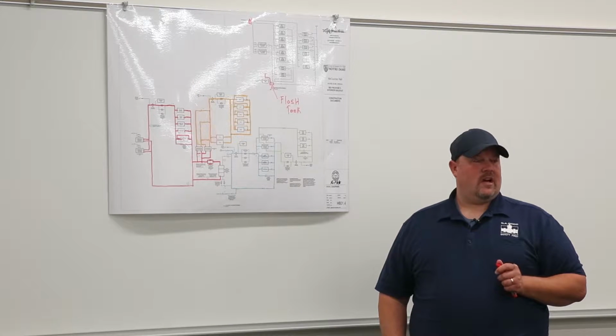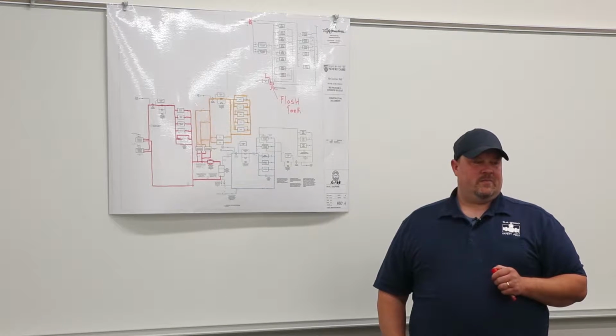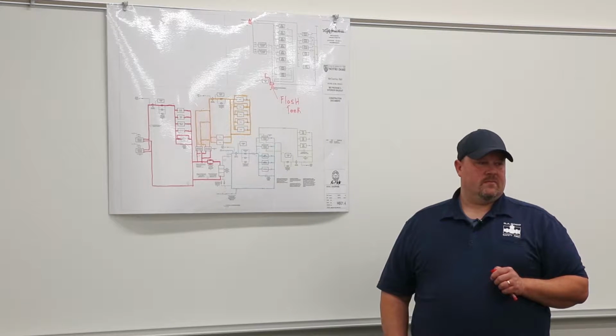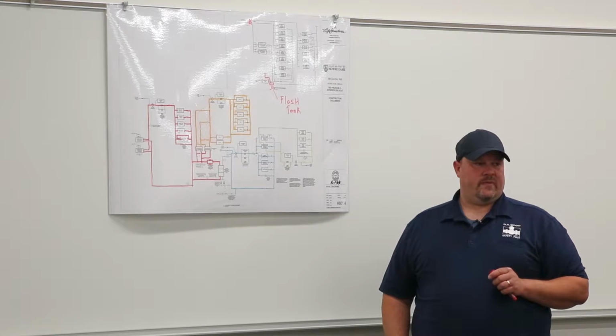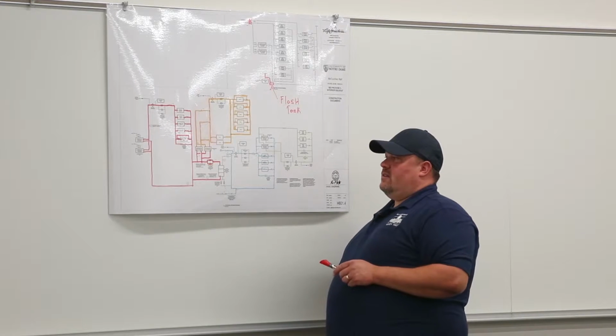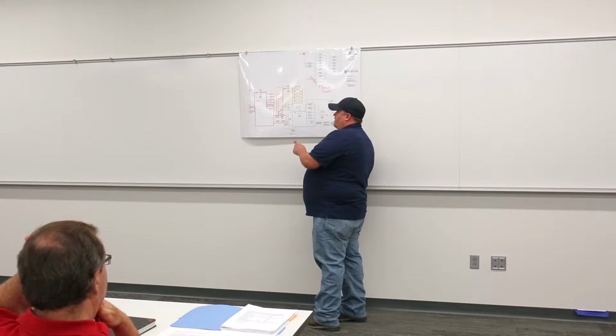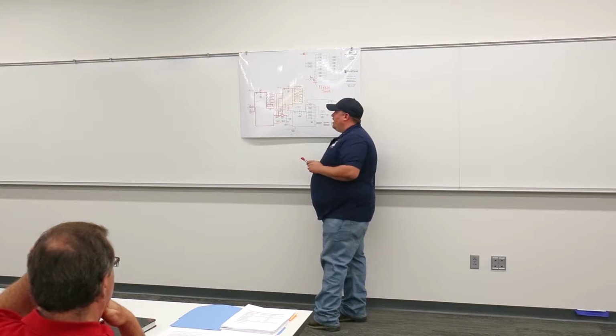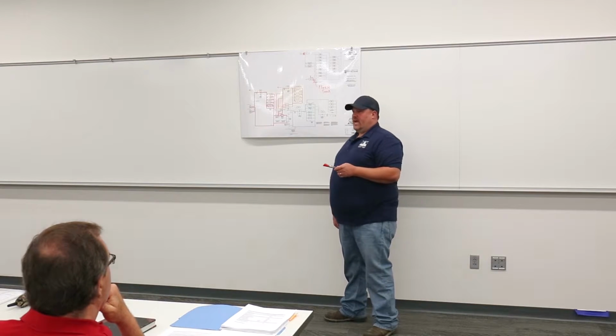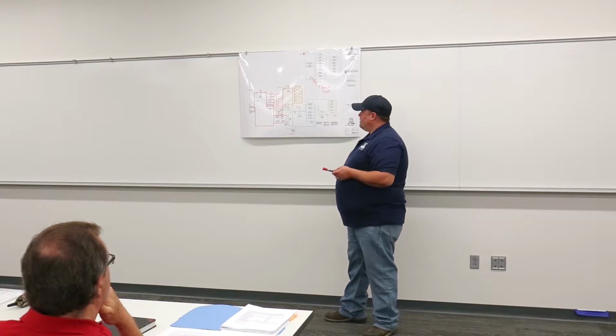That's a very good point, I know because you had brought that up. Yeah, the guys will see this, but in the first year, they recommend that you blow that down every month, just because of a new system and new stuff that's in there. And after that, maybe once every 6 months or so. This air and dirt separator, they recommend it be blown down every month of its first year of use. And then after that, in 6-month intervals, it requires a blowdown.